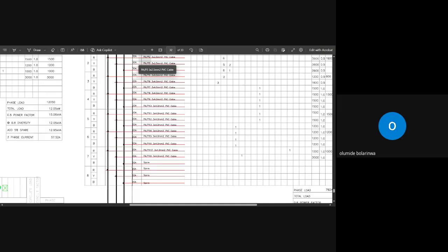So 4 times 100 equals 400 meters of 20 mm conduit pipe you want to use. Remember that the 4 meter average has an excess that will cover the piping going to your switches.